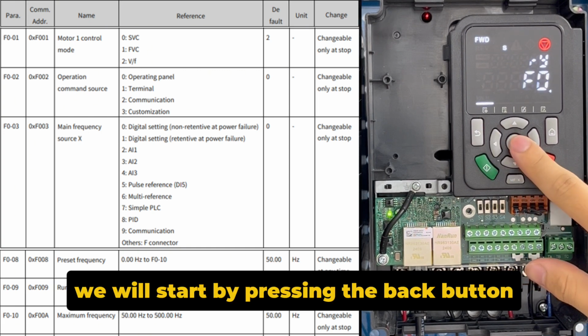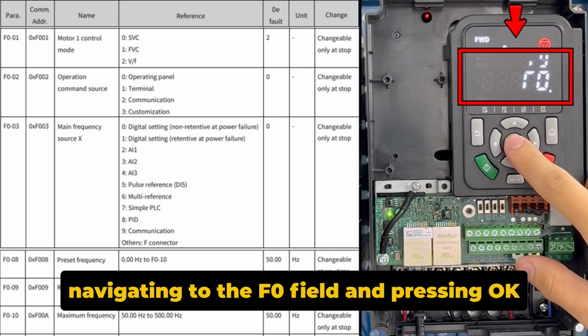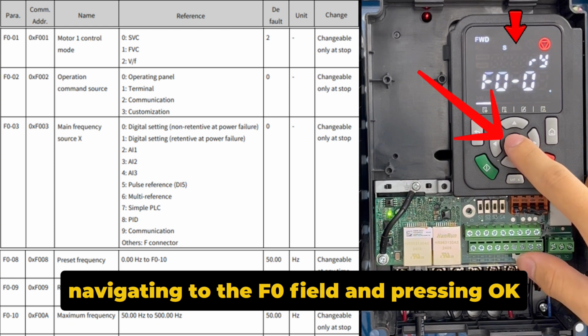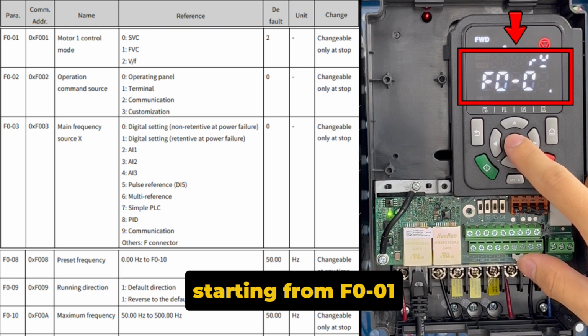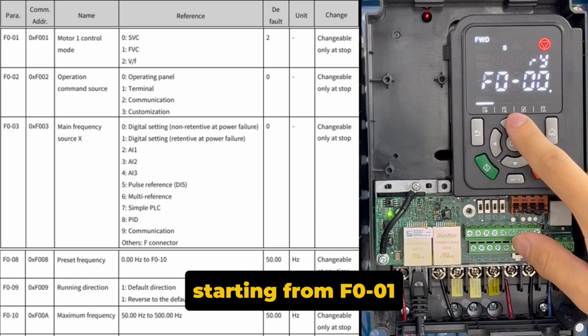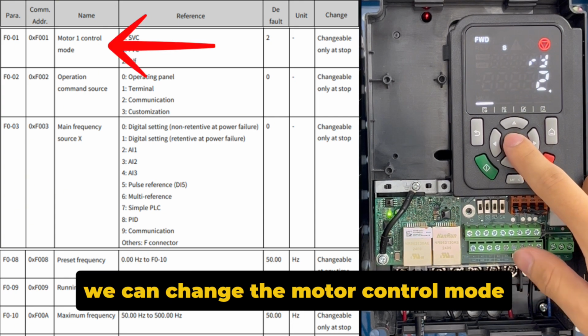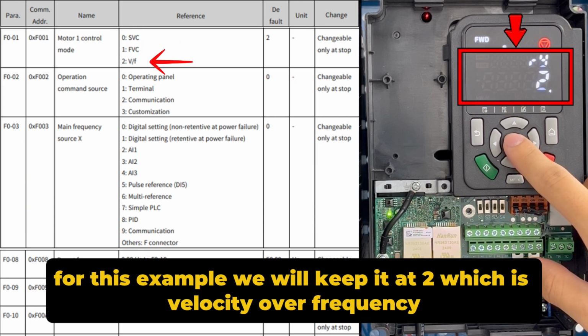We will start by pressing the back button, navigating to the F0 field, and pressing OK. Starting from F0-01, we can change the motor control mode. For this example, we will keep it at 2, which is voltage over frequency.